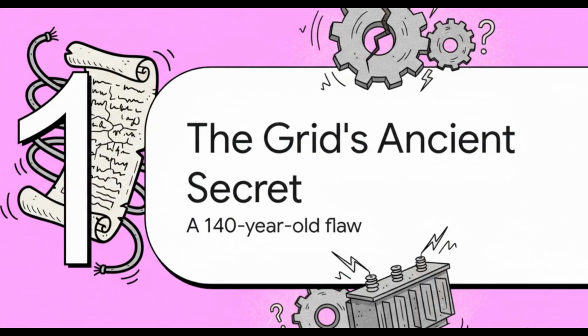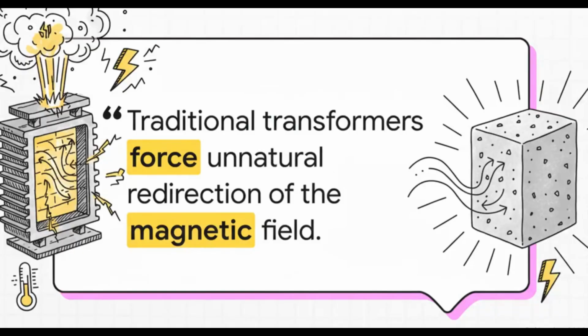The problem isn't just that the tech is old. It's that the core idea has a built-in flaw we've just been working around for more than a century. The key word there is force. Old school transformers grab a magnetic field and literally jam it through a steel core. This act of forcing the field to go where it doesn't naturally want to go creates resistance. And resistance means wasted energy, a ton of extra heat, and limited performance.